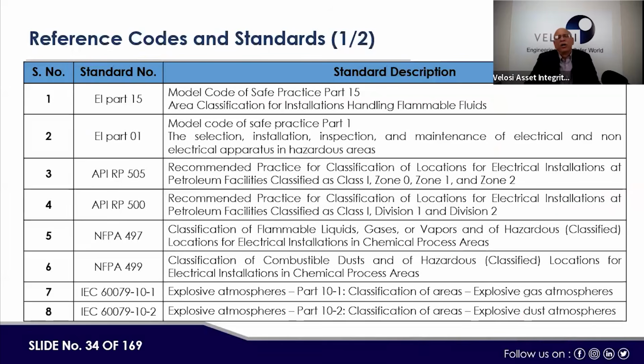So the reference standards which are available to go by or to develop the HAC process. Previously, the standard was IP-15. Now the new name is Energy Institute 15, which we normally call EI Part 15. Then Part 1 is there, and API RP, previously 500, and then 505 was introduced. These are two American standards. People who were familiar with hazard area classification in the past compared IP-15 and API RP 500. Now the Americans have also developed API RP 505, which is comparable with IP-15 or EI-15 or EI Part 15. Similarly, NFPA 497 and NFPA 499 are also guidelines for HAC classification.